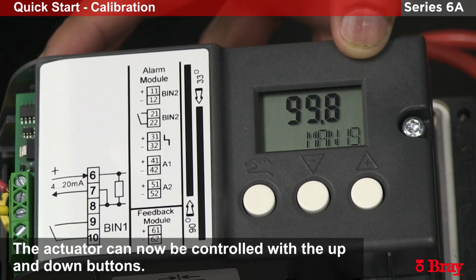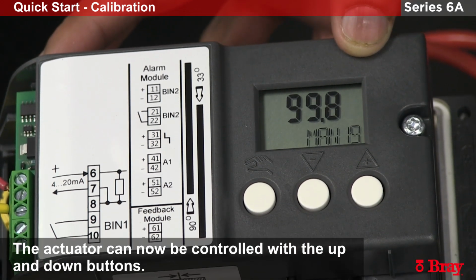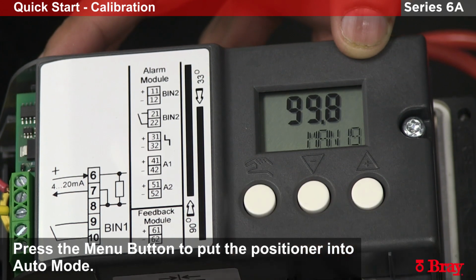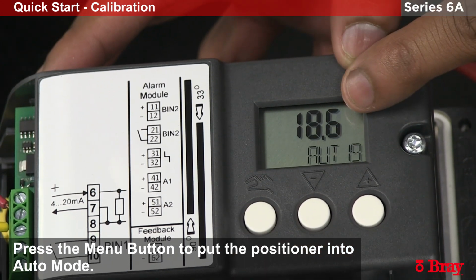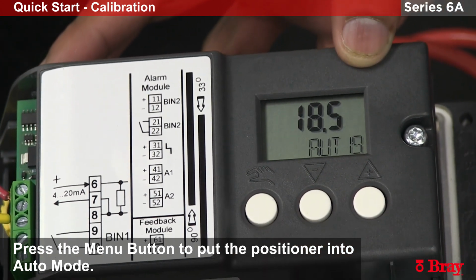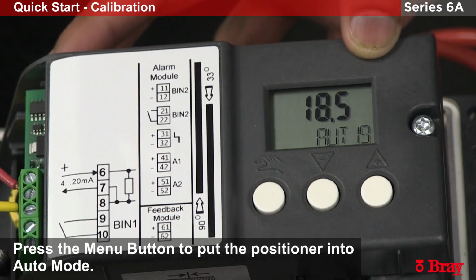To put it in auto mode so it listens to the 4 to 20 milliamp signal, we'll hit the hand button once, and it'll state auto in the bottom right. Now the positioner is ready for service.